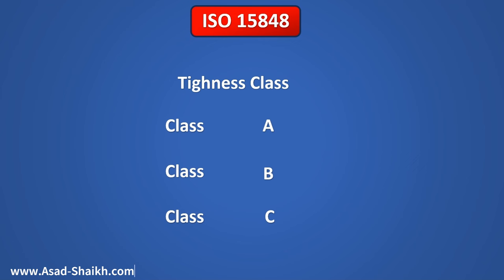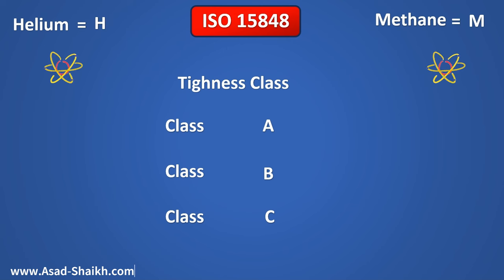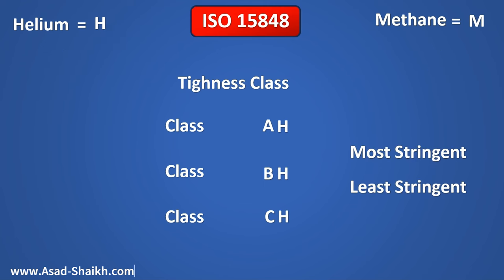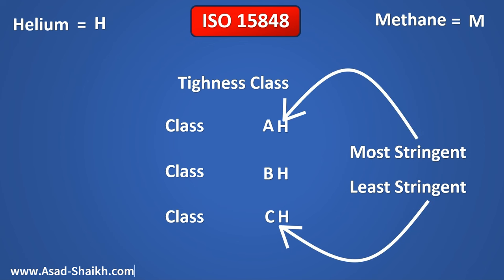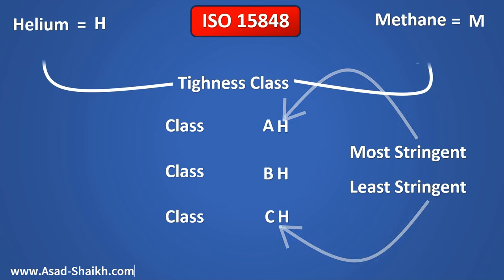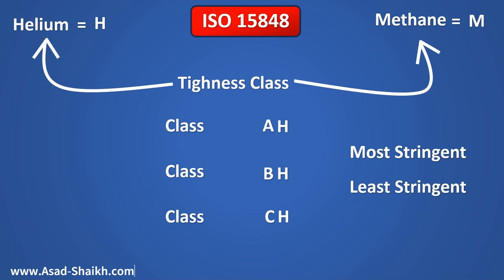Going further into ISO 15848, the tightness class is very important. The class is divided into Class A, Class B, and Class C, with the test gas being either helium or methane, defined by H and M respectively. So for helium you have AH, BH, and CH. Class A is the most stringent while Class C is the least stringent. If you use methane instead, you have AM, BM, and CM.